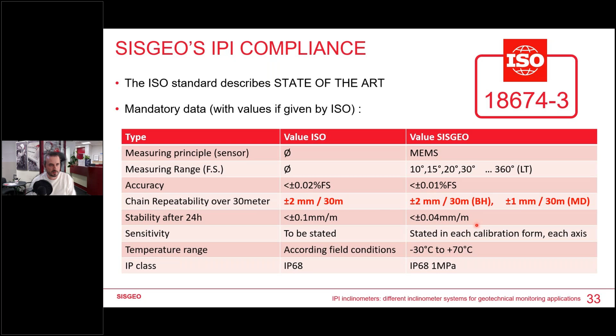But as I said, mechanics, the way you install the casing, it's much more important because the final result depends not on the system accuracy, but on the full chain accuracy, the repeatability and the stability. Here, as you can see, the norm has plus minus 2 millimeters for 30 meters of system, so manual system or automatic system. Here, the BH is compliant to exactly this value, but the MD is 2 times more accurate, more repeatable, let's say. So this is a value that you have to pay attention to when you purchase your system. To date, Sisgeo is the only manufacturer to comply with all its inclinometers IPIs. I have verified.